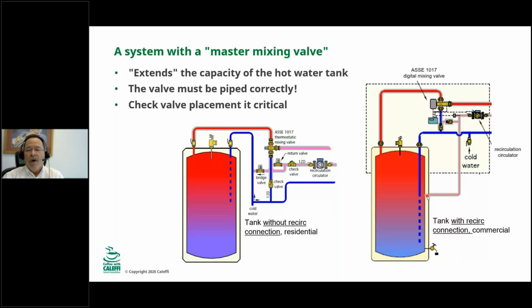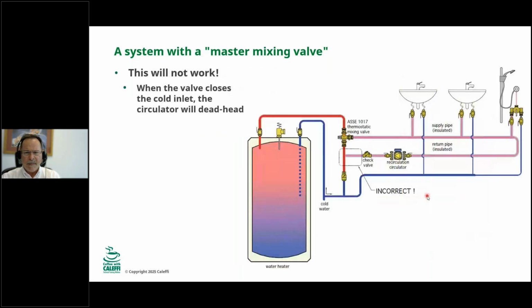This won't work, okay? If you have a recirc connection that comes back and just tees in right here, that's not going to work. Why? If this valve closes the cold inlet port, the recirculation circulator is going to deadhead because the water can't go in here, it can't go into the mixing valve, and it's not going to go backwards through this check valve. So that's one main reason.